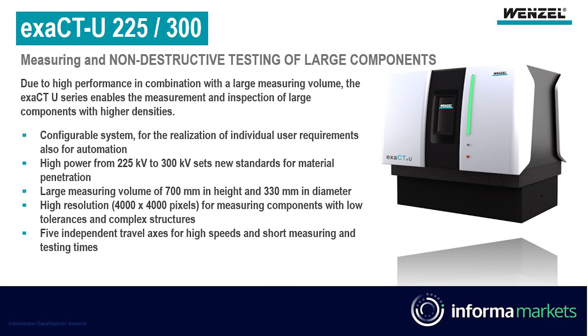So the X-ray tube itself is an open X-ray tube. Basically, that means that you can take the X-ray tube apart and rebuild it. So if you're running the thing 24 hours a day for 6 months, you can take it apart and make it pretty much like new. You replace the filament physically, you clean the inside, you put new connectors in it, and the machine runs for life.